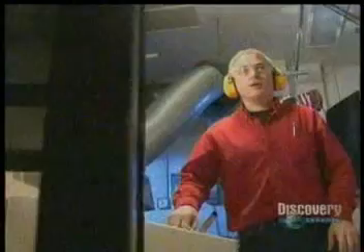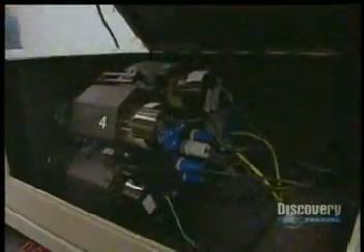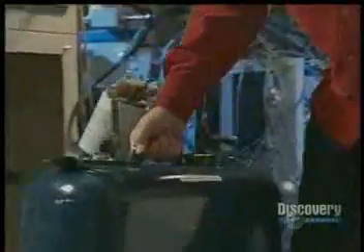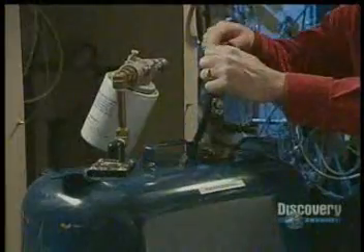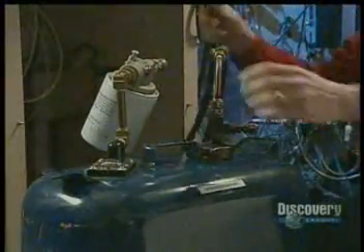The Kettering staff took about a week to shift the main facility from automotive engine testing to the jet turbine experiments. Sensitive equipment was tested and calibrated with a number of trial runs. Test day began with the purchase of 5 gallons of randomly selected commercial jet fuel from the local airport.